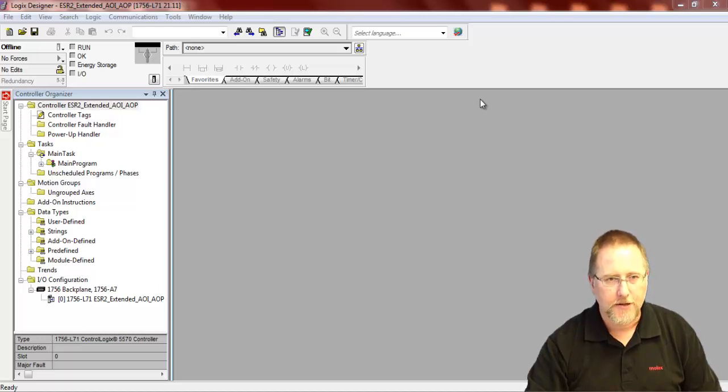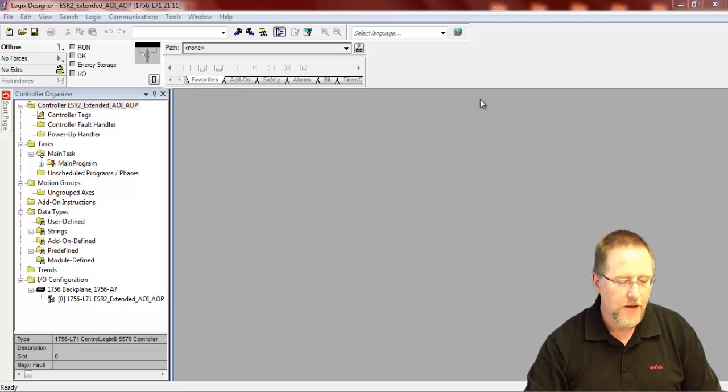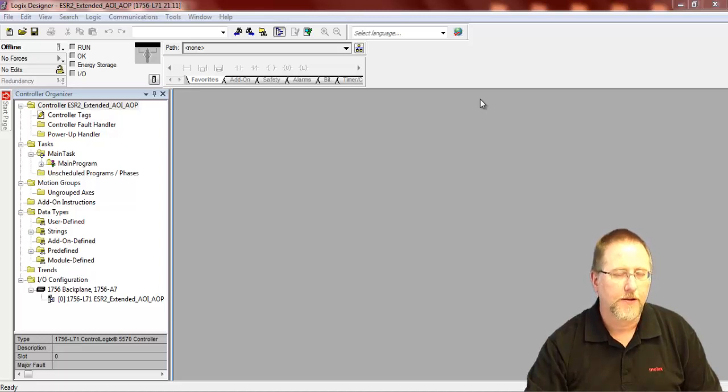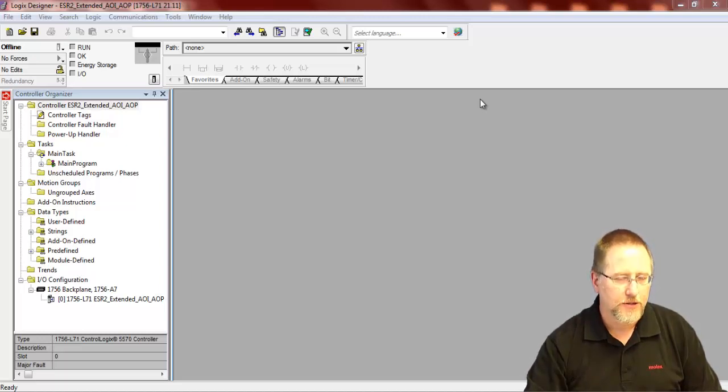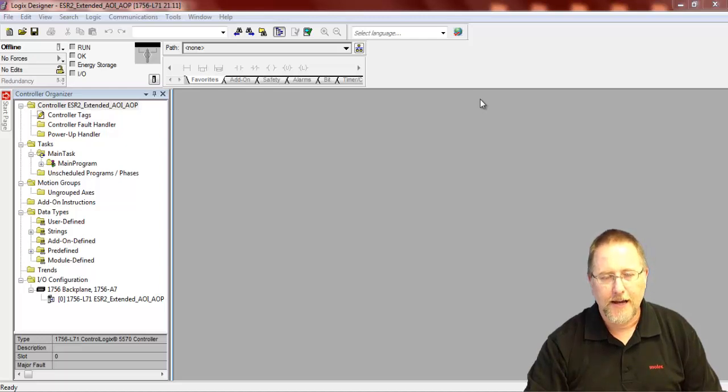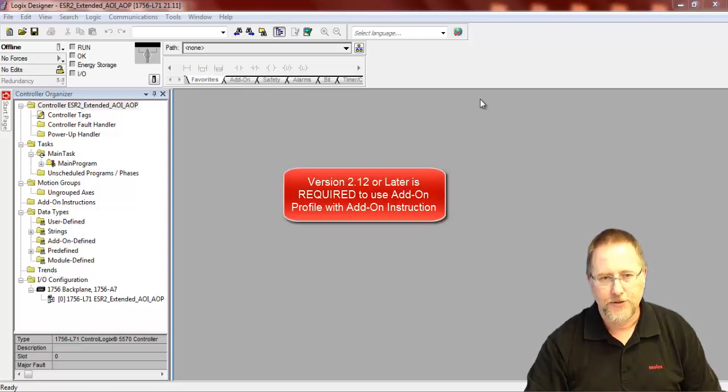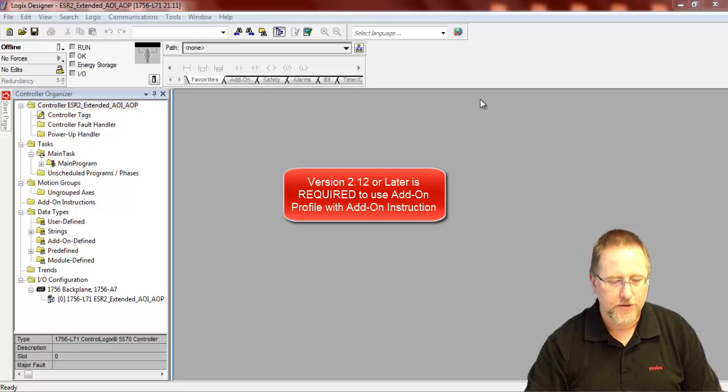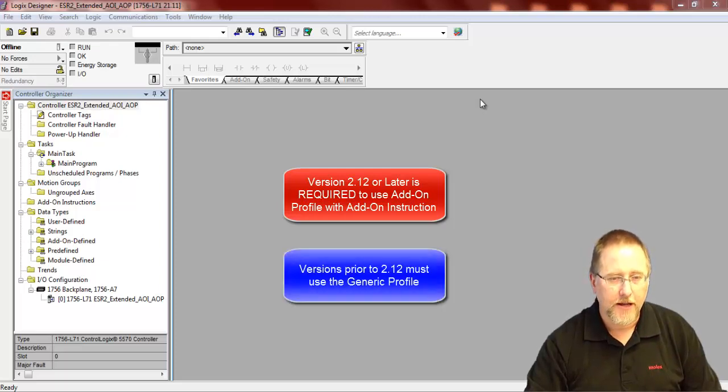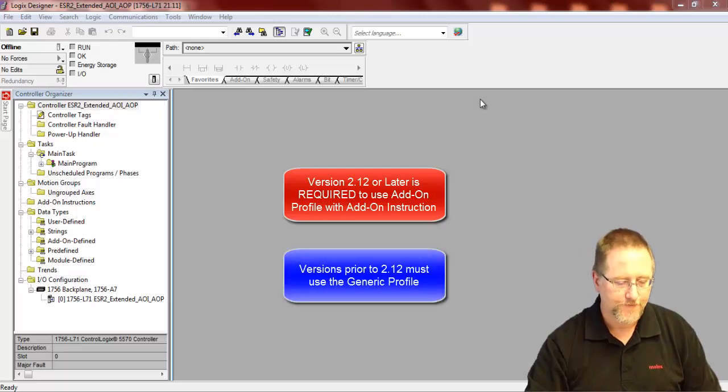Let's set up the ESR2 module. One of the restrictions for using the add-on profile here is the firmware version on your ESR2 or SR4 module has to be version 2.12 or later to use the add-on profile with the add-on instruction. Prior to that, you have to use the generic profile.